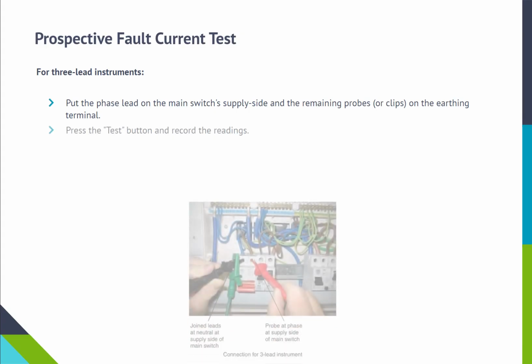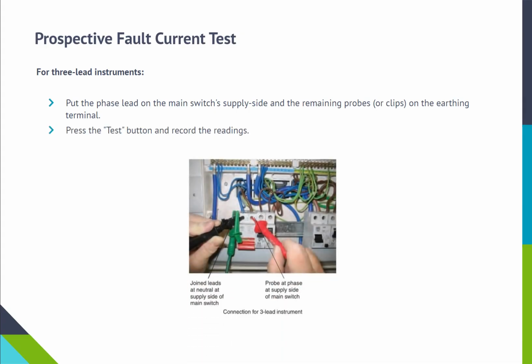For 3 lead instruments, put the phase lead on the main switch's supply side and the remaining probes, or clips, on the earthing terminal. Press the test button and record the readings.